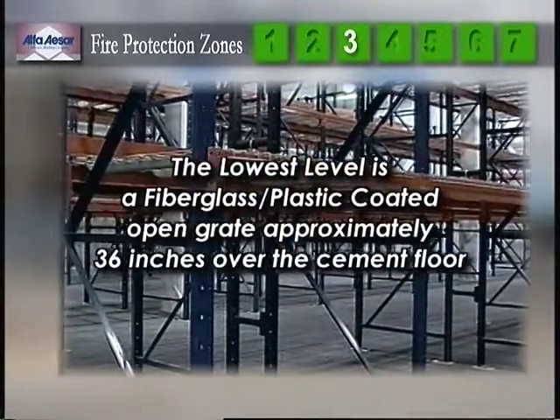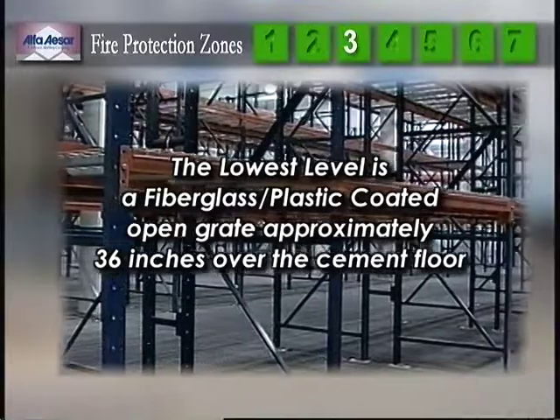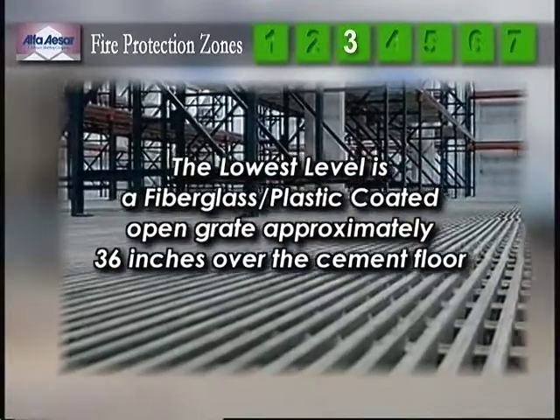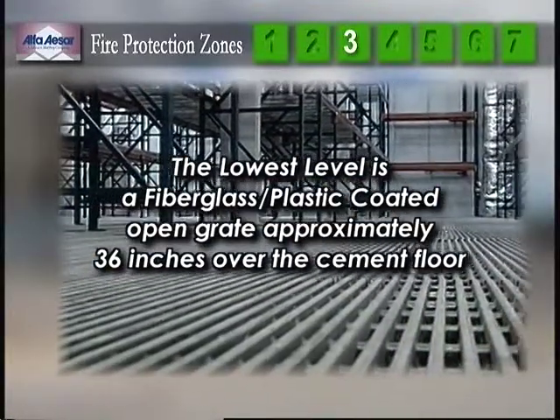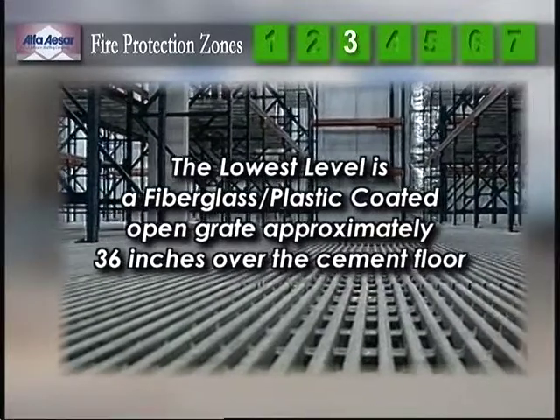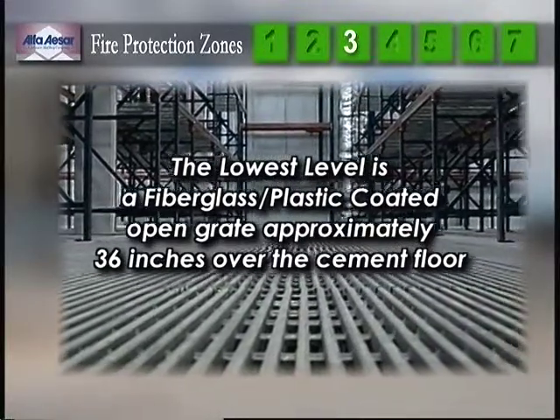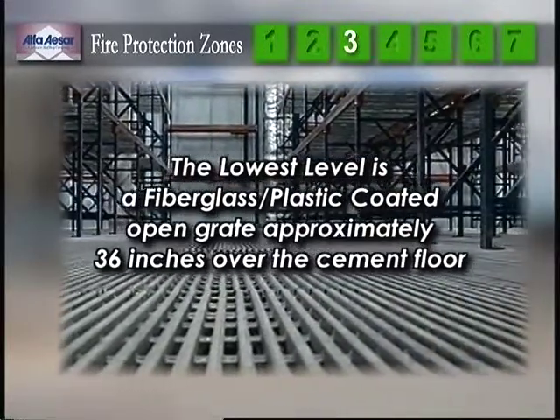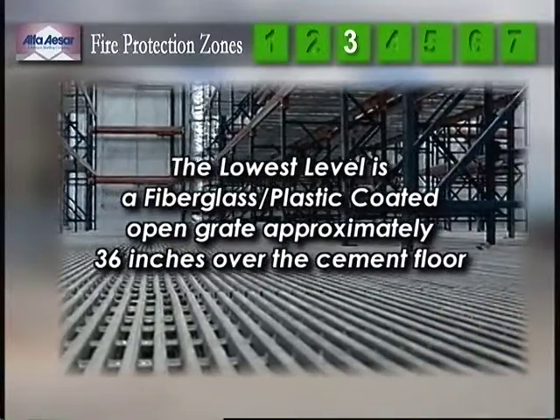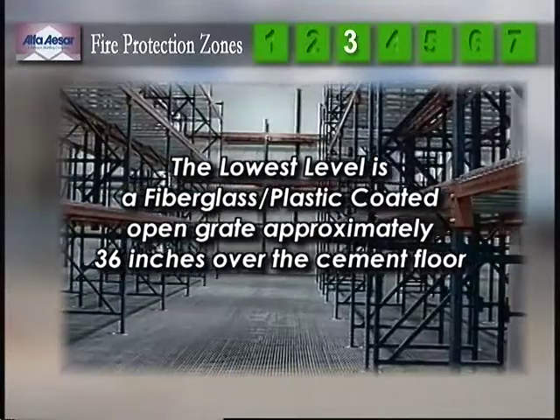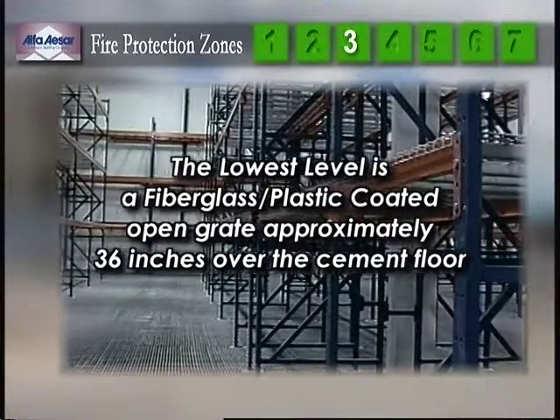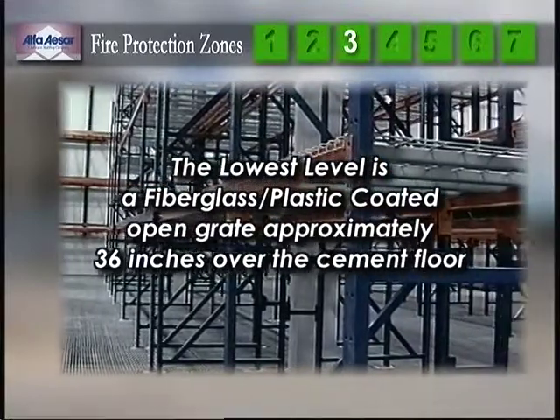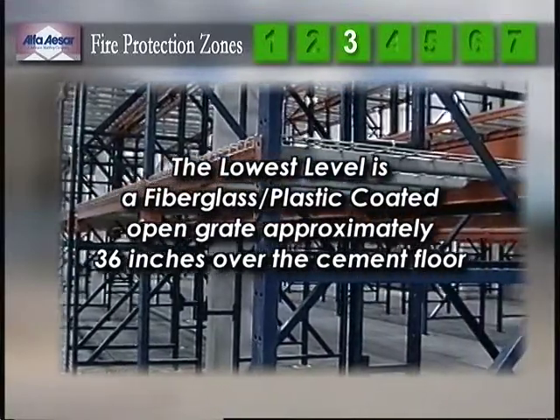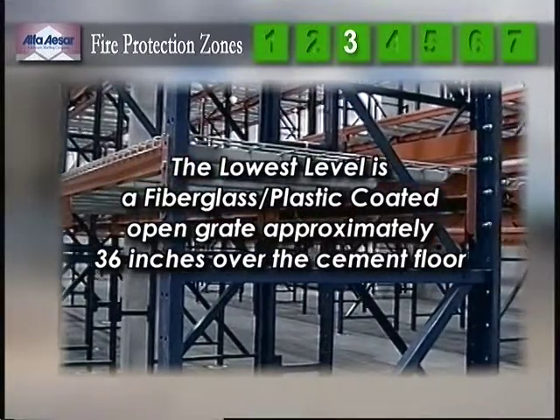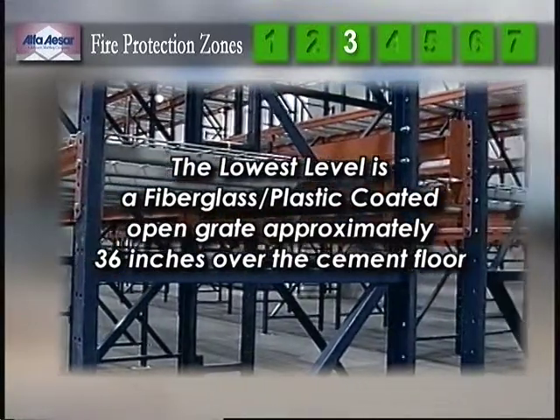Product is located on wooden pallets arranged in a rack system. The lowest level of storage in the rack system is a fiberglass plastic-coated material that forms an open grate floor, through which any spilled liquids will fall in the event that the integrity of a container is compromised. The coated nature of the surface is intended to mitigate the formation of sparks. A concrete floor is located approximately 36 inches below the open grate floor to capture spilled liquids and any release of the AFFF extinguishing system.